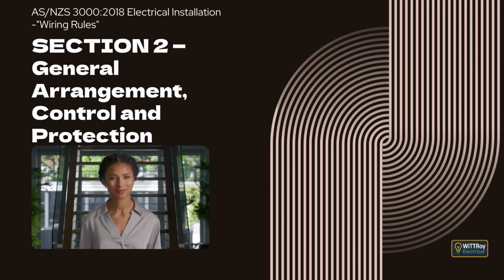Clause 2.6.2.4, Arrangement. When additional protection is required for final subcircuits, the RCDs must be arranged to minimize inconvenience and avoid losing supply to large parts of the installation. In any installation where there is more than one RCD and more than one lighting circuit, the lighting circuits must be shared between RCDs so only part of the lighting is lost if one device trips.